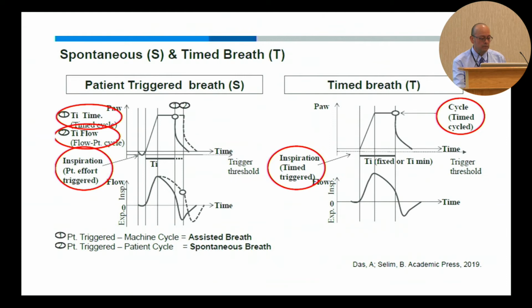The Respironics device, it depends. This number one is the machine breath. This number two is the effort breath, that is the patient, and the flow changes. So I think it's important that when you're doing your titrations, you know, first of all, which brand you are using. Are you using Respironics or ResMed? And second, you need to understand a little better what the inspiratory time is, and to which breath it is being applied.